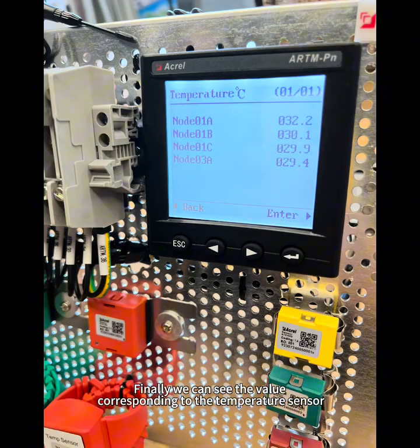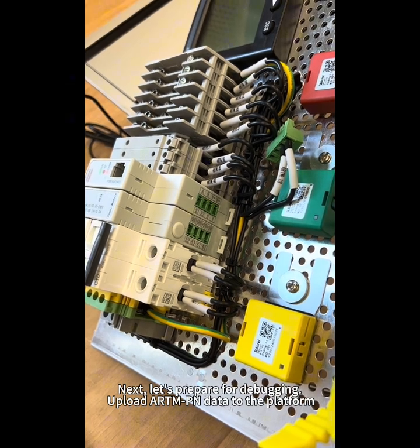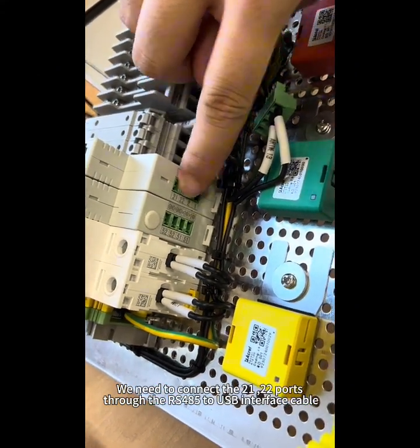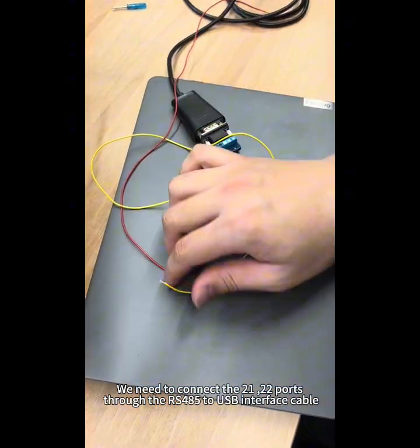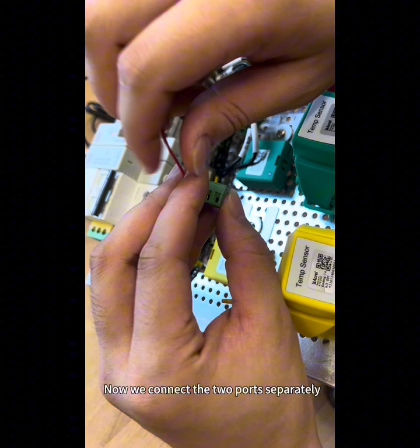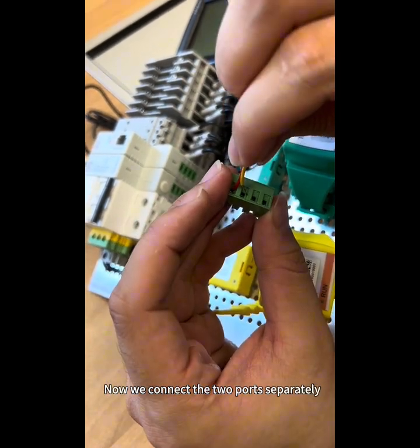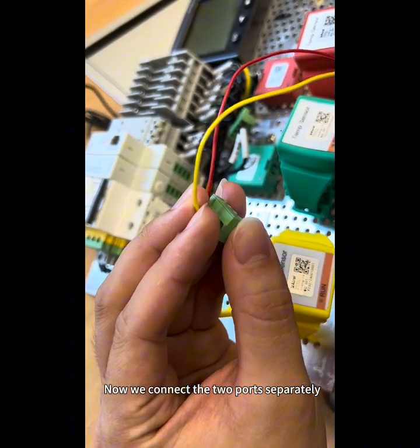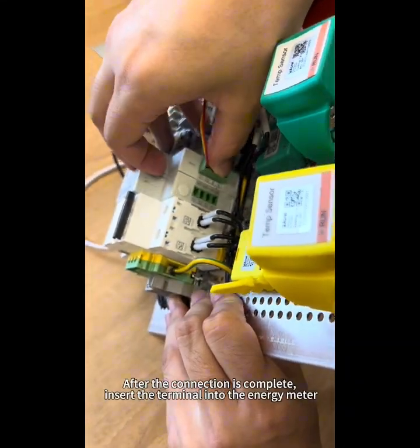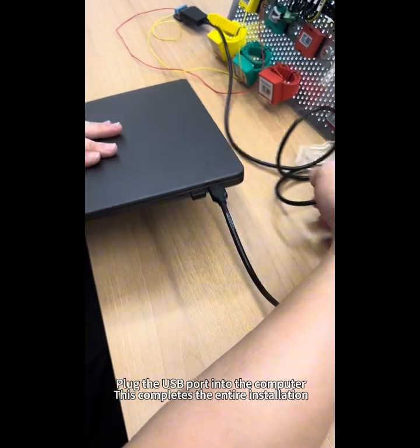Finally, we can see the value corresponding to the temperature sensor. Next, let's prepare for debugging and upload ARTM-Pn data to the platform. We need to connect ports 21 and 22 through the RS485 to USB interface cable. Now we connect the two ports separately. After the connection is complete, insert the terminal into the energy meter and plug the USB port into the computer. This completes the entire installation.